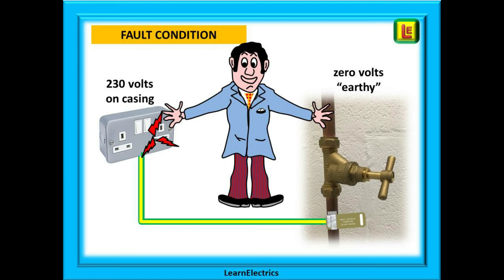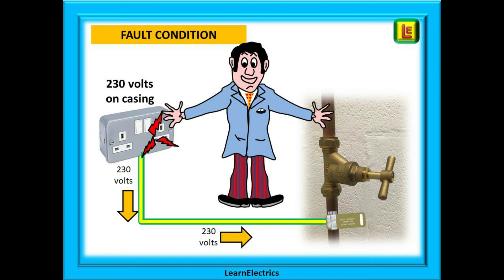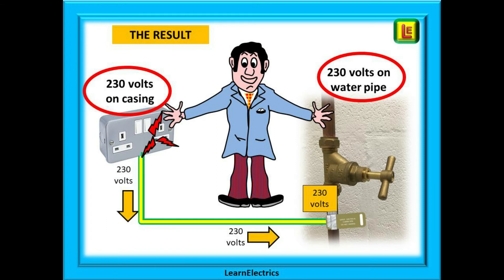If we had a bonding cable between the socket and the water pipe, things can be a lot different. The same fault as before — the socket casing becomes live whilst Eric is plugging in his radio. The 230 volts travels along the bonding cable and appears at the water pipe, making the water pipe 230 volts as well. So what have we got? One hand on the socket casing at 230 volts, the other hand on the water pipe also at 230 volts. A little arithmetic: 230 minus 230 equals zero volts. There is therefore no voltage difference across Eric's body. Ohm's law tells us that if there is no voltage difference then there cannot be any current flowing.